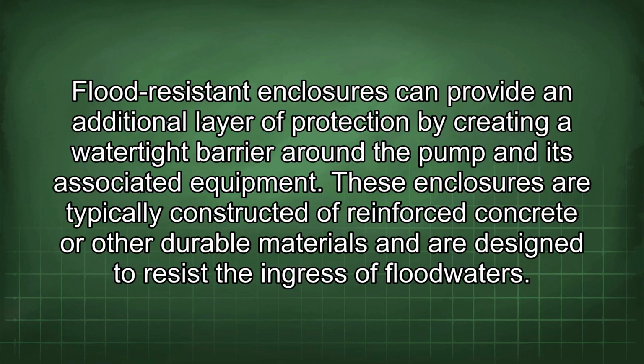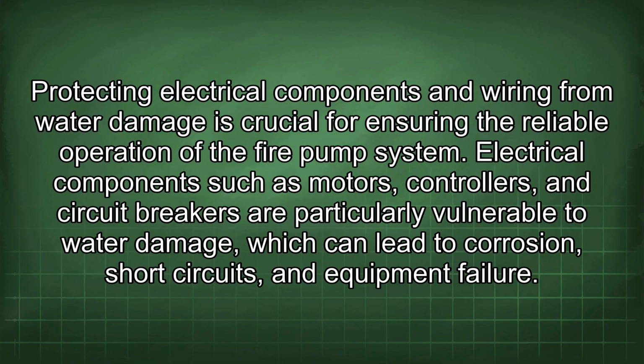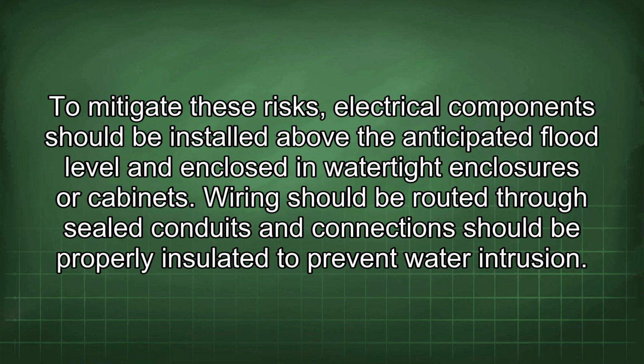ingress of floodwaters. Protecting electrical components and wiring from water damage is crucial for ensuring the reliable operation of the fire pump system. Electrical components such as motors, controllers, and circuit breakers are particularly vulnerable to water damage, which can lead to corrosion, short circuits, and equipment failure. To mitigate these risks, electrical components should be installed above the anticipated flood level and enclosed in watertight enclosures or cabinets. Wiring should be routed through sealed conduits and connections should be properly insulated to prevent water intrusion.